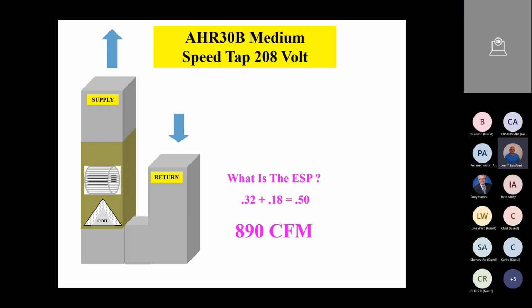So 400 CFM per ton is the nominal airflow we're looking for based on the tonnage of the outdoor unit. So this is a 2.5-ton air handler, but it could be matched up with a 2-ton unit outside, based on the application. And so we're actually blowing a little bit more air than we need for a 2-ton unit. Any questions or comments on this first example? We're going to do several more just to make sure everybody's squared away with this.